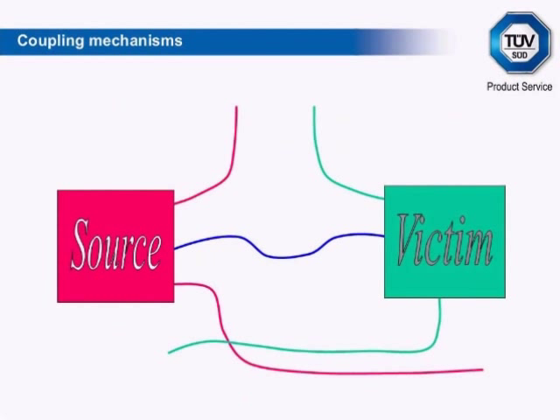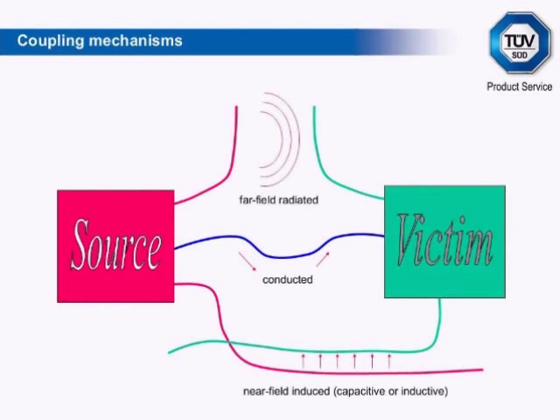Coupling mechanisms: putting source and victim together shows the potential interference routes that exist from one to the other. These can be identified as: 1. Conducted — through a direct connection from one to the other. 2. Near-field induced — by proximity of structures such as cables which have significant mutual capacitance or inductance. 3. Far-field radiated — where the structures behave as receiving or transmitting antennas.